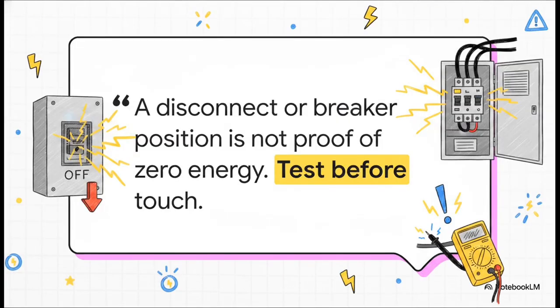Here is the absolute crucial point. A disconnect or breaker position is not proof of zero energy. Test before touch. Off doesn't necessarily mean dead. You might look at a disconnect handle, see it in the off position, but you literally cannot trust your life to a piece of plastic. Internal contacts inside a switch can weld themselves closed due to heat or wear, leaving the circuit fully energized even when the handle says it's off.